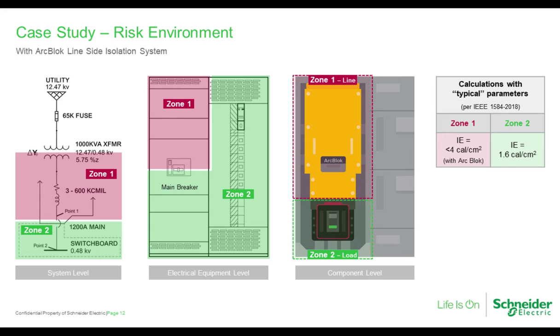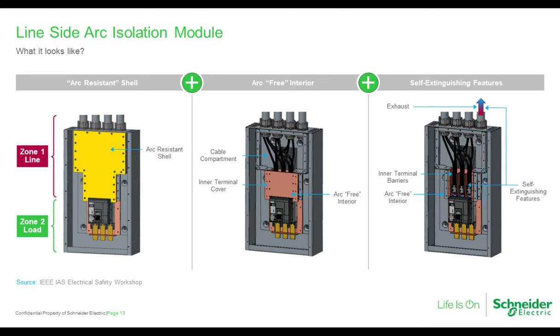This solution is created by building what is essentially a miniature arc-resistant enclosure in which special features have been added to make it exceptionally good at arc management, both in how it treats the arc directly and how it handles its byproducts. So let's take a look inside. Looking under the hood, the recipe on this slide says line side arc isolation module, which is another word for ArcBlok. And we can see it revealed in 3 steps.